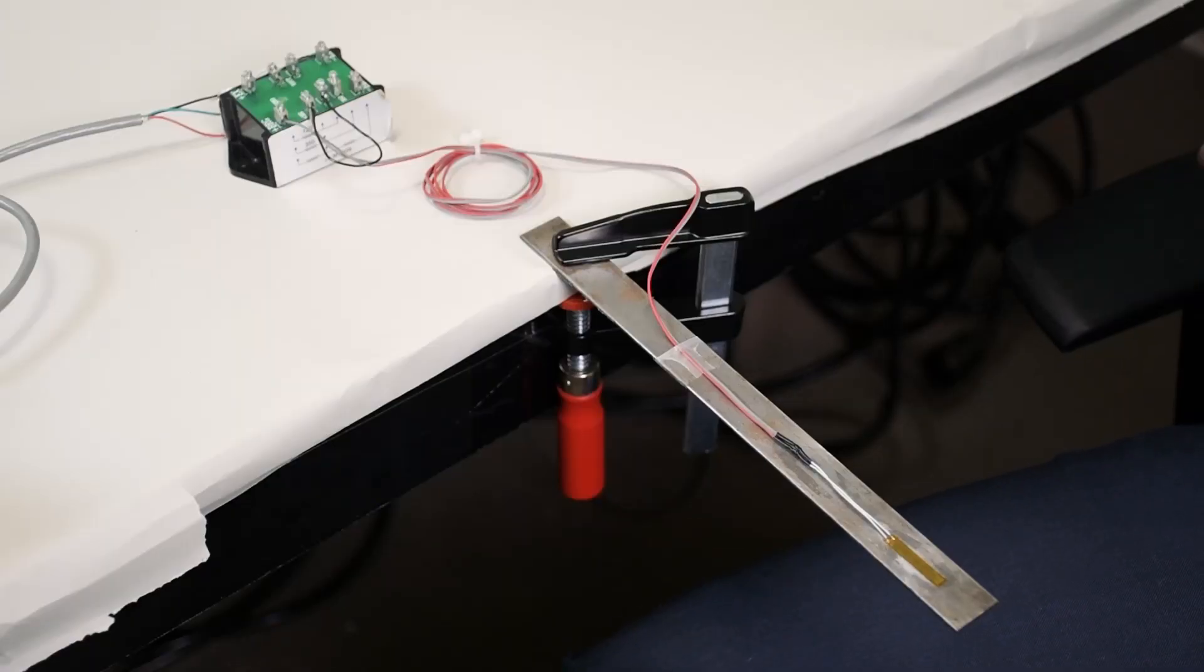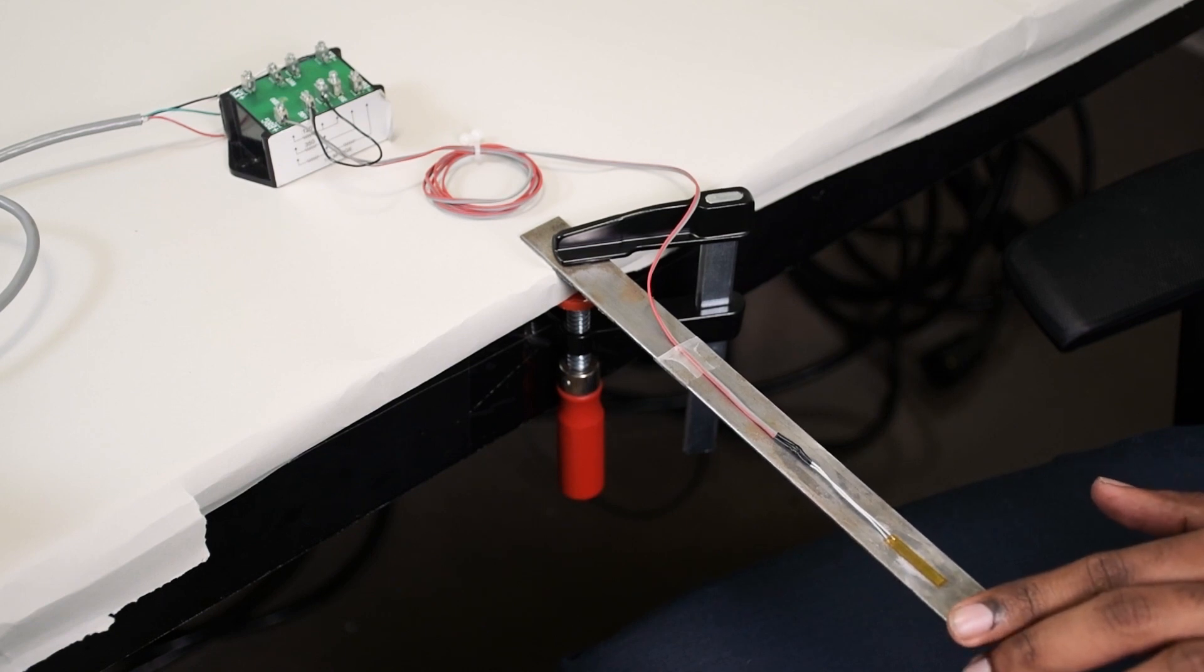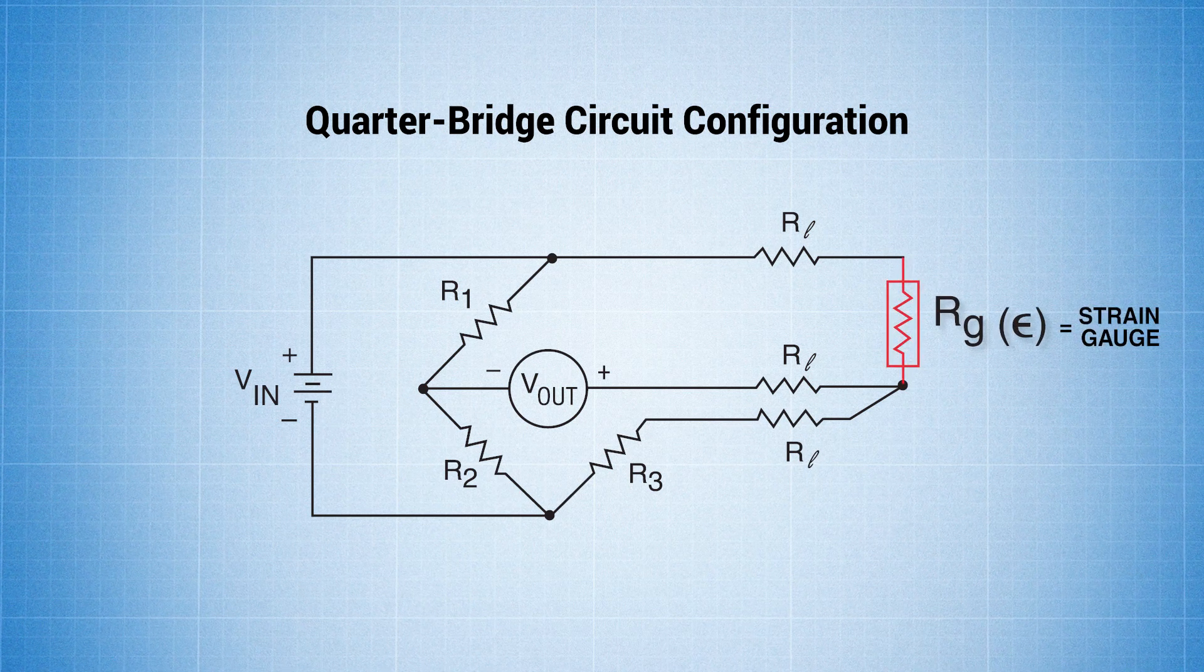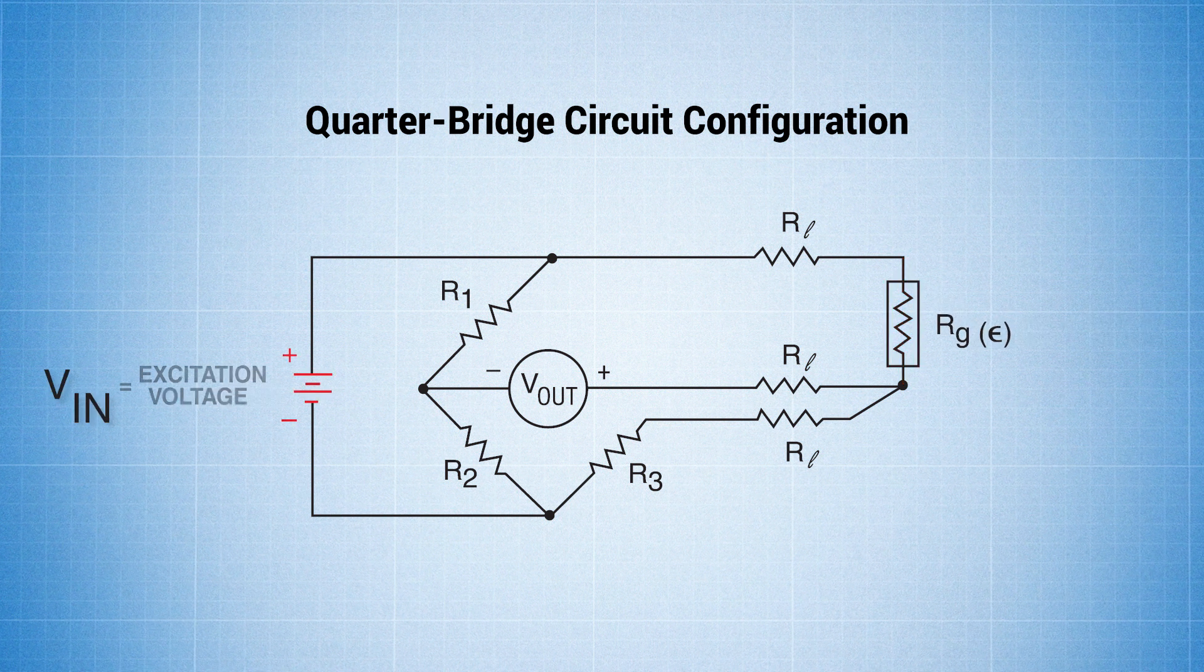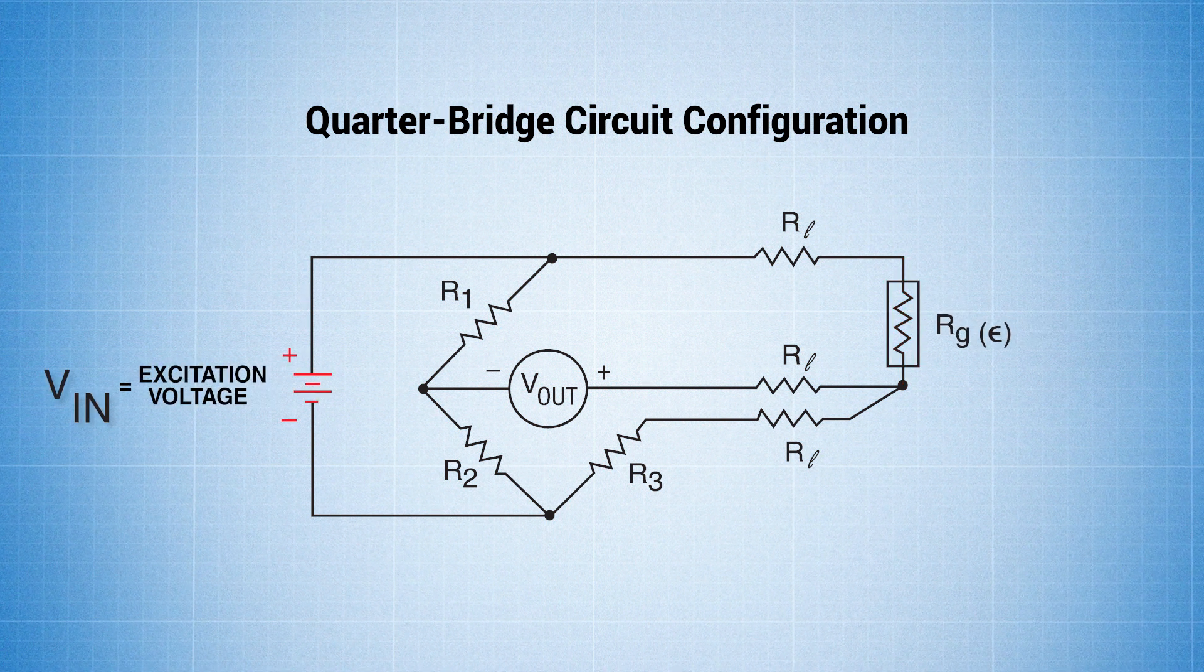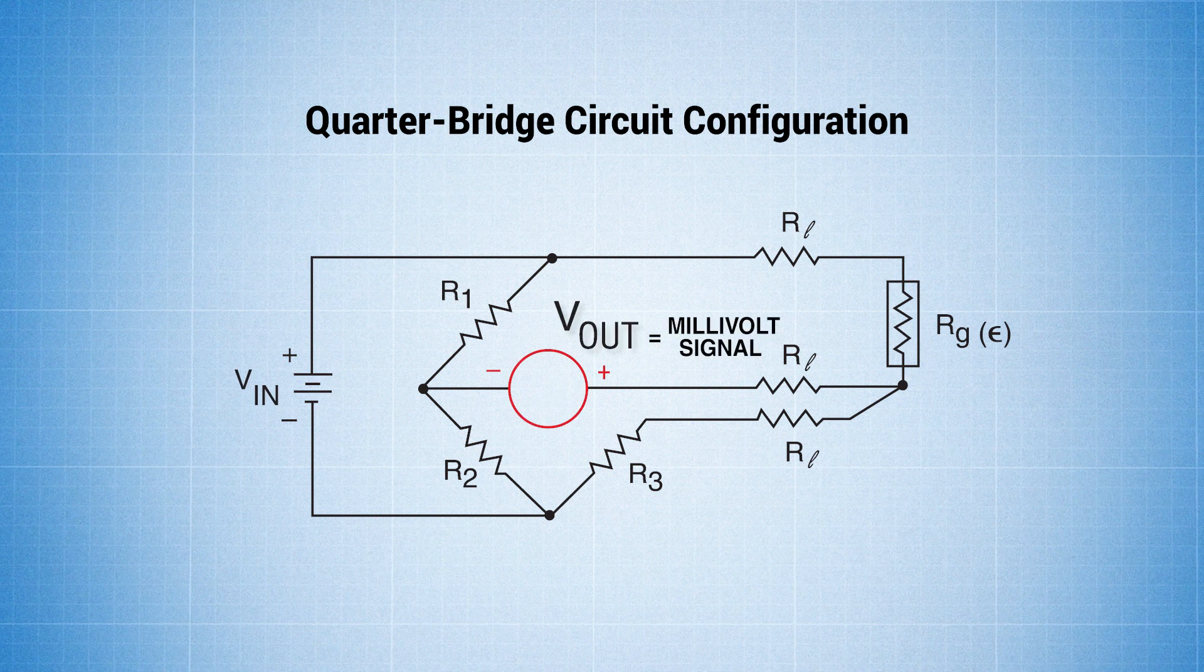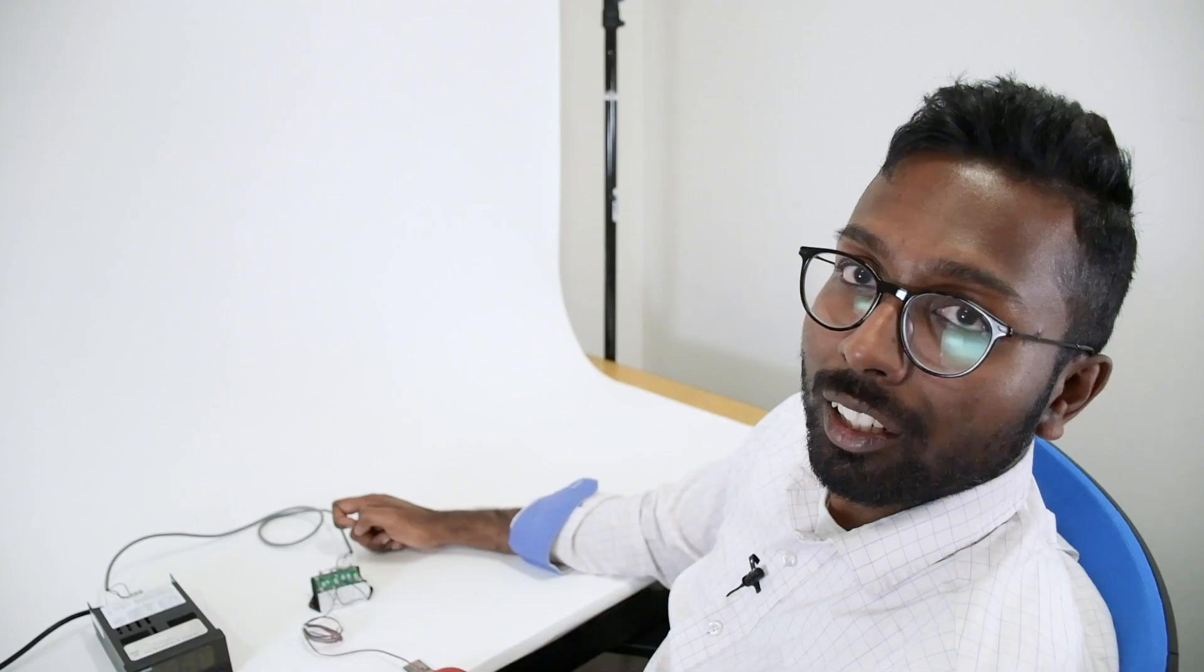If you look at this configuration, there's just one active strain gauge, so this constitutes a quarter bridge in the Wheatstone network. In the quarter bridge configuration, Rg is the strain gauge that we have bonded onto the stainless steel flat, Vin is the excitation voltage going into the Wheatstone network, and Vout is the millivolt signal that we get from the BCM that goes back to the DP25B-S unit.